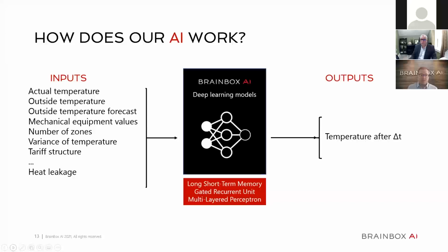And this example is showing an LSTM type deep learning model. And then what it outputs is the future prediction. So like in other industries, that predictive nature of self-driving cars, where it can predict when somebody is going to walk out in front or the red light is going to stop or whatever, it is taking that prediction. And now that we have the prediction, that 2 to 4 hours in advance future state thermostat, think of it as another thermostat on the wall, we can use that future prediction to optimize the sequence of operations in the building to be more efficient, to improve comfort, to mitigate demand charges, and a lot of other things. Next slide, please.